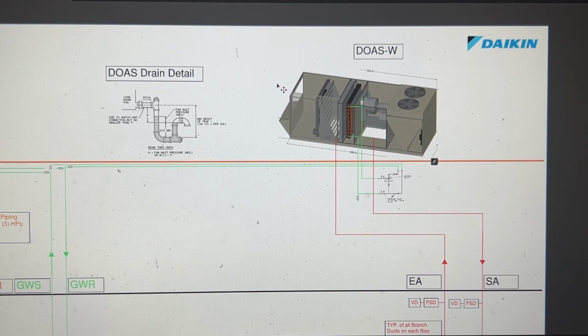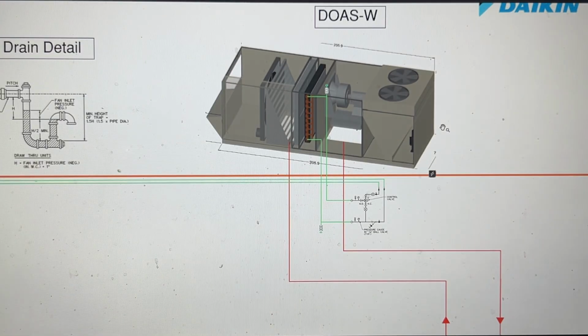So just to recap: rooftop unit, outside air, depending on the condition, it gets tempered one way or the other to what is ideal, and it's pushed down as ventilation air for all of the floors. The heating component will be glycol. The cooling component is the DX coil in the unit. Now, the only thing is the controls portion of it. This is a self-packaged unit, so we could go into that controller and set everything to the parameters that we want, and this thing will run sufficiently on its own independently, and we could BACnet it back to the BMS system.